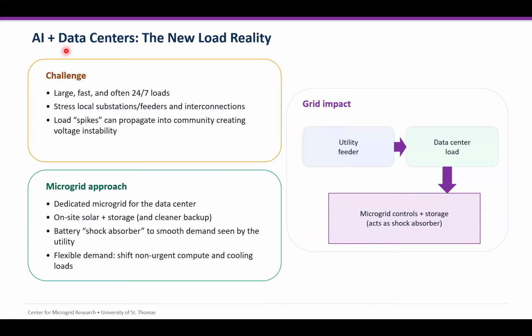One of the developments in the application is AI and data centers, which are considered the new load reality as well. The challenge is that they need large, fast, and often 24/7 loads. It puts some stress on the power grid, the feeders, and the interconnection. Also, they are training new models, so you'll find a peak or a spike in the load usage, which, if it gets propagated through the feeders, can cause some voltage instability for customers as well.